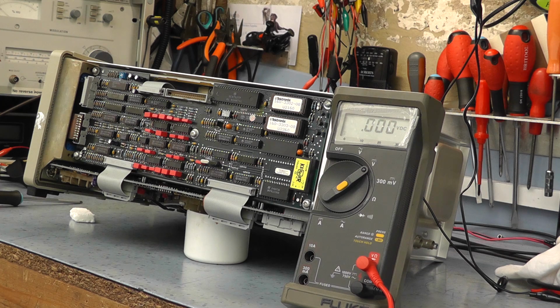I'm not exactly sure what that is. It's something to do with the non-volatile memory or the checksum error. That's what, according to the manual anyway. Now I don't know if we've lost our settings already and it's totally out of calibration, or it's just something wrong with the scope and it's just flagging up a sort of erroneous error.